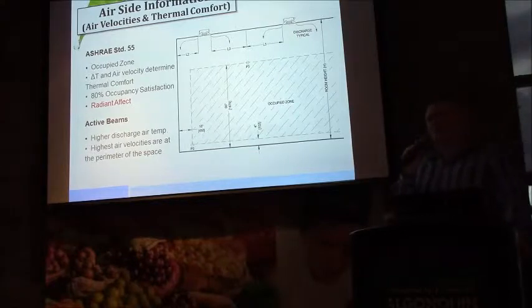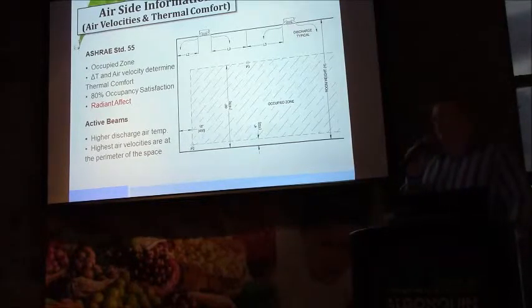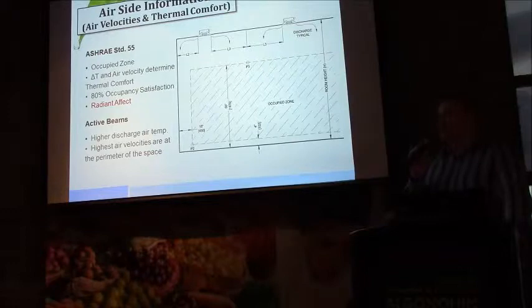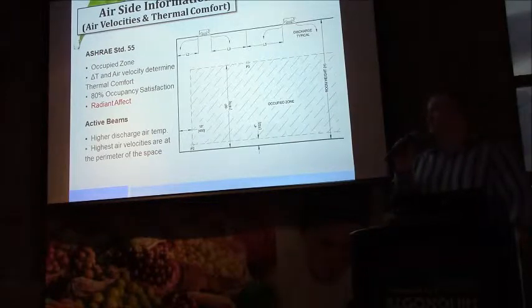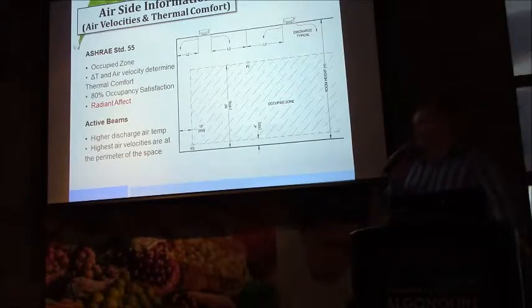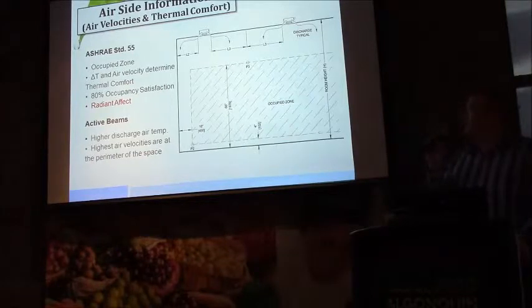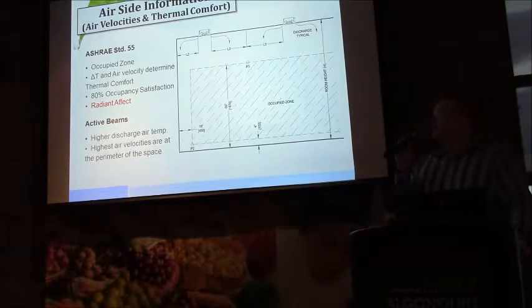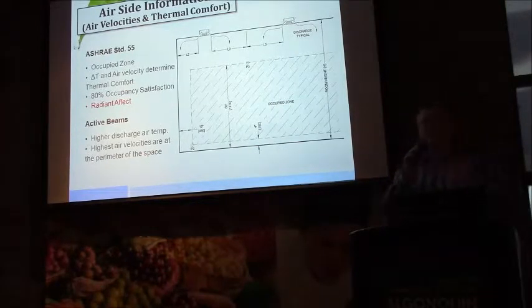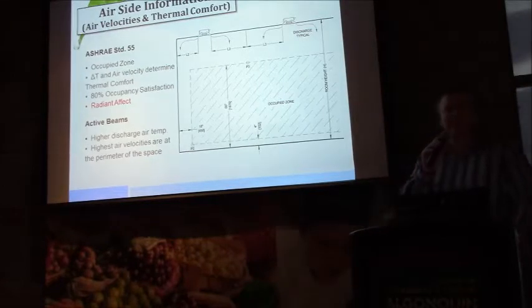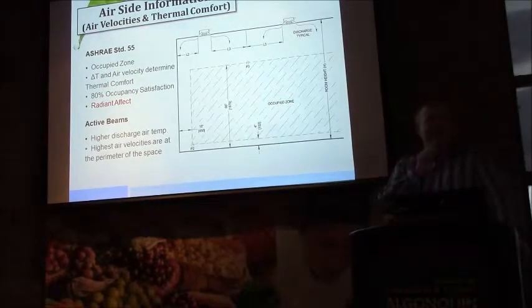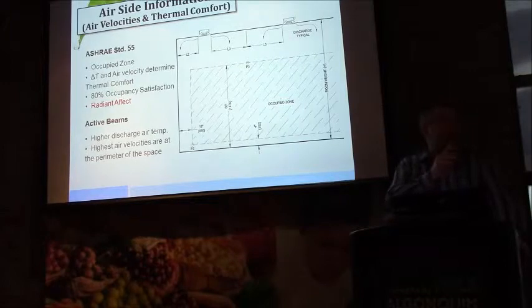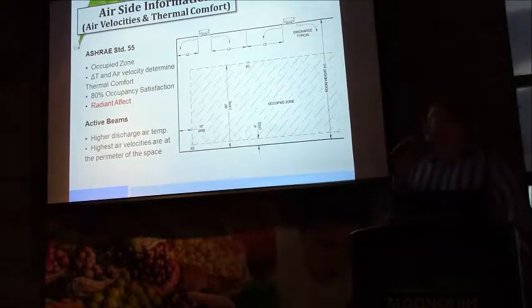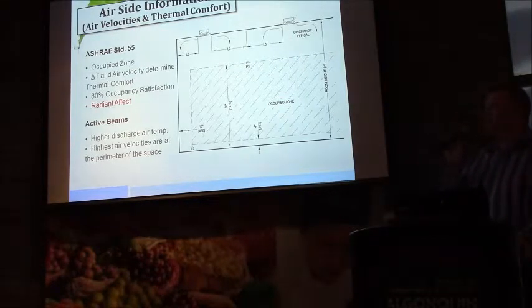Essentially, the L2 dimension, or the placement of the discharge of the beam, can also be a talking point relative to controlling the glazing surface temperatures. And so in the event that we discover that much of the load comes from the glass, and we can mine this information from the psychrometric calculations, the load calcs, we may choose to bias the discharge of the beam closer to the glazing in order to ensure that we are managing the glazing surface temperature adequately, preventing radiant asymmetric comfort issues.